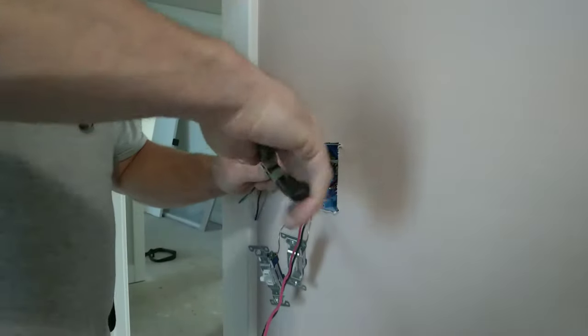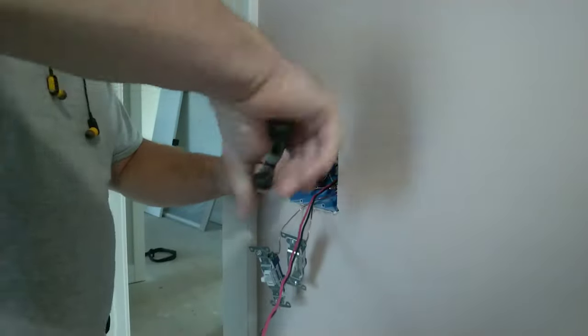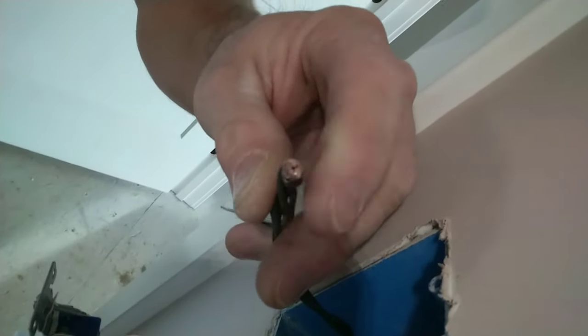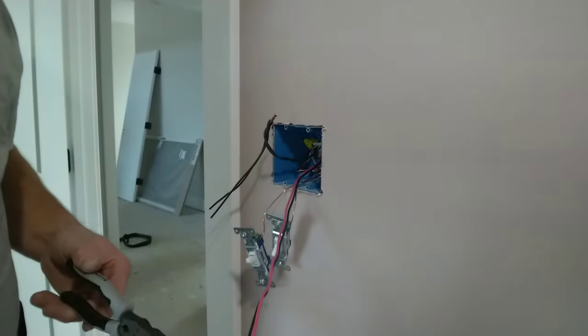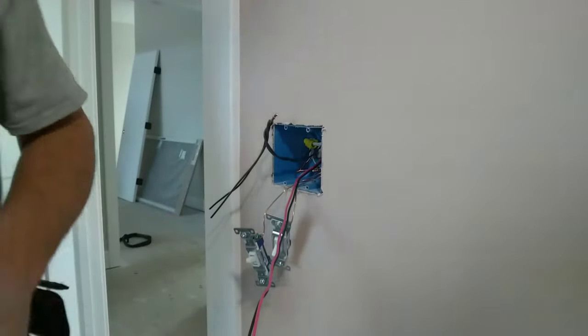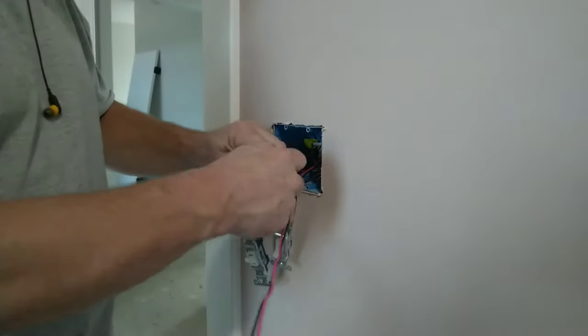We're gonna get our alignments, and we're gonna start spinning loosely. Now on this one, I'm gonna show you up close what it looks like. All right, we've spun it. We have spun that. It's nice and tight. Now what I'm gonna do is I'm gonna take and snip the ends off, holding the camera doing this at one time. All right, so if you look at the very end of this, you see all four wires. One of them's not shorter than the other, they're even. Put you back on the stand, and we are gonna use a tan wire nut. We're twisting together four 14 gauge wires now.